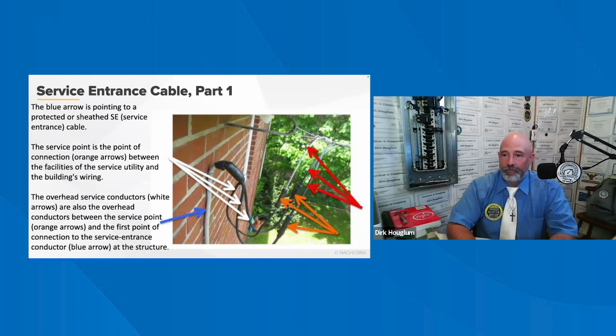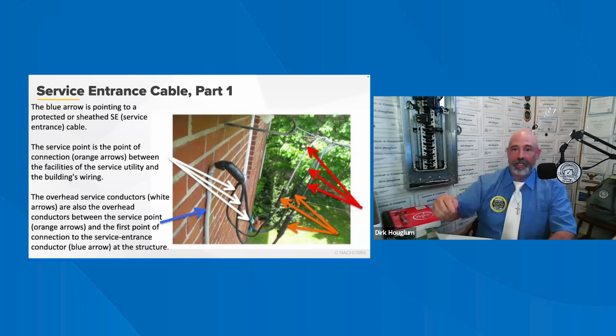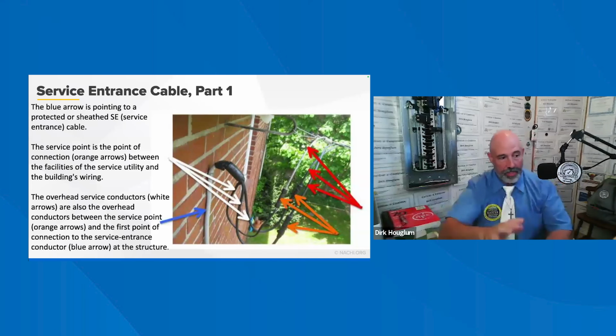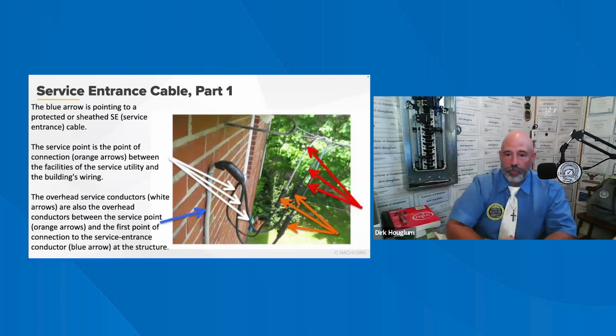The overhead lines coming from the power company, right there. So you can see how it dips down, goes into that drip loop. So we want to make sure that for inspectors, we are looking at that service drop. We're looking for that drip loop there, the wires feeding into the house, and we're looking for the splices or the taps.